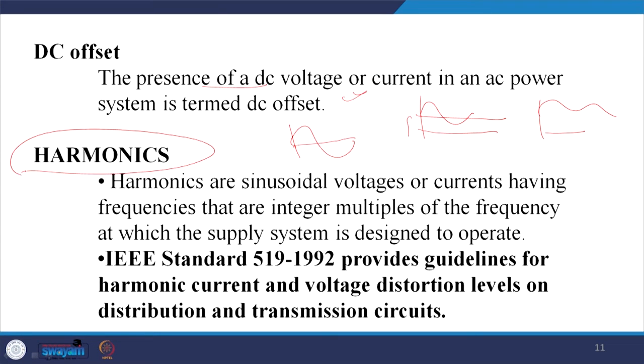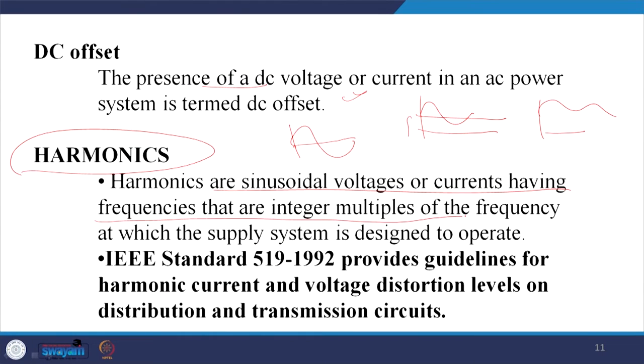Harmonics are the most dominant entity in power quality. Harmonics are sinusoidal voltages or currents having frequencies that are integral multiples of the frequency at which the supply system is designed to operate — IEEE standard 519, basically the 1992 standard, which has since been updated. It provides guidelines for harmonic current and voltage distortion levels on distribution and transmission circuits.